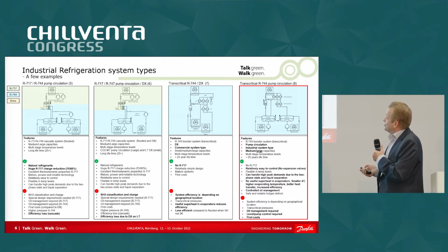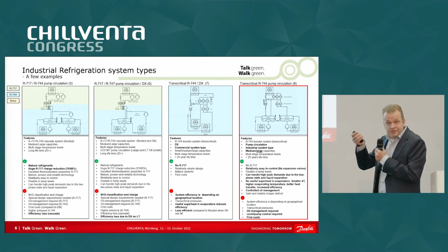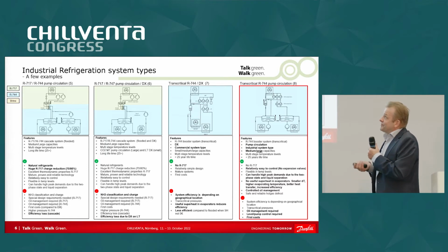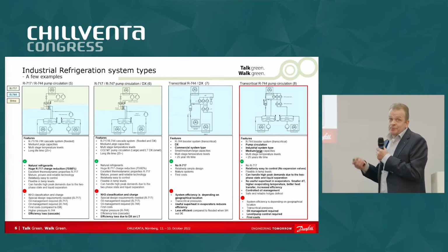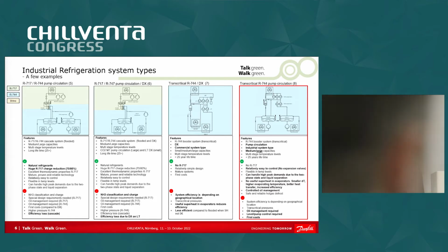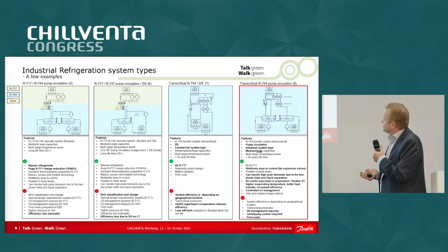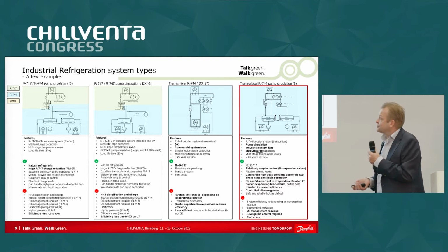There's no ammonia anymore, but because we are sometimes in a transcritical state, transcritical phase, the efficiency really depends on the ambient temperature and the place where you build the system. So geographically, where is the system built? So that could be a negative thing, but you have to be aware of it. And this is DX, so you have superheat. You have to have superheat, otherwise how to control. So you have some efficiency loss because the more superheat, the more delta T you have across the evaporators.